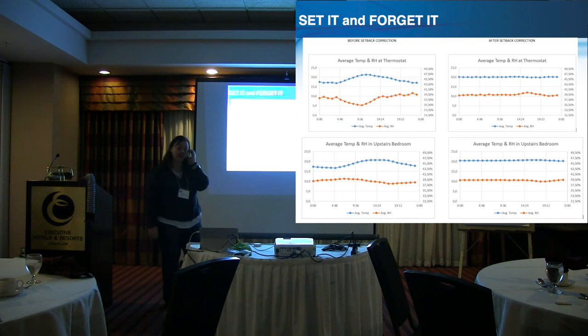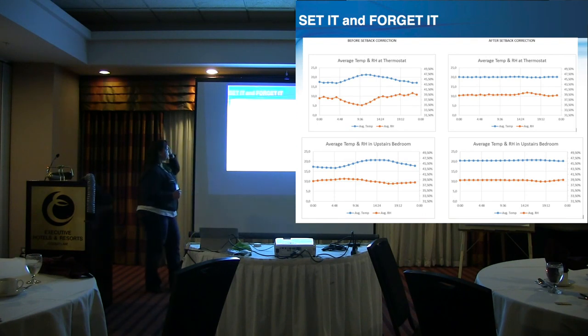So we were also monitoring relative humidity. When the engineers saw this, they were like, uh-oh, that's not what we designed. You can see on the top left there, relative humidity is in orange, blue is the temperature. And we don't want to see that variance between those two. Temperature isn't the problem in new construction or any house really, it's the relative humidity. So when we get a nice continuous airflow, that's when we see that correlation to balance.